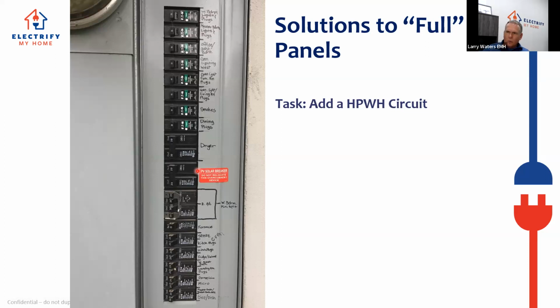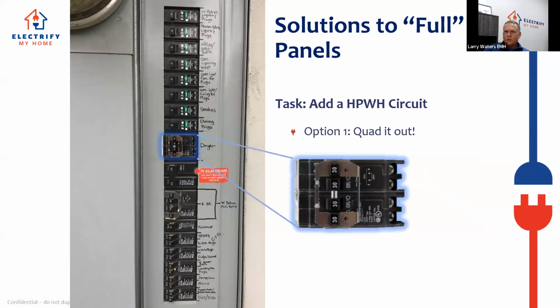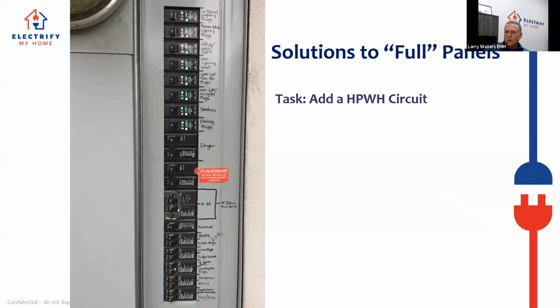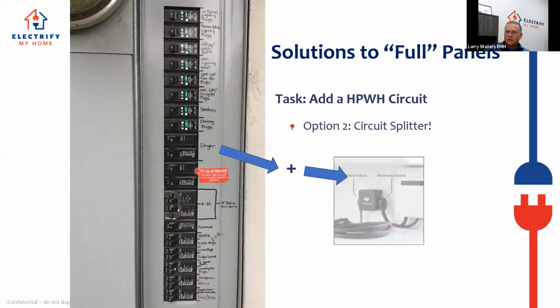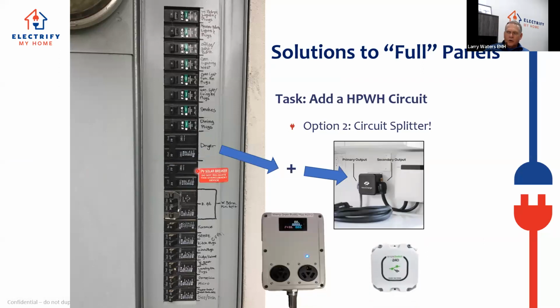So what do we do if we want to add a heat pump water heater circuit to this panel? The first thing we would probably do is quad it out. We'd take that dryer breaker out, and put a 30-30 quad in there. Or we could use a circuit splitter. For you guys that don't know about these, circuit splitters are amazing devices. This is one right here.